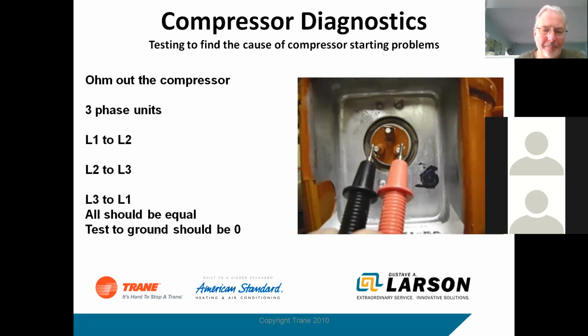The difference is, if you look at a true three-phase compressor, it's going to say L1, L2, and L3. And on an inverter-driven piece of equipment, you're going to see U, W, and V. That's an international symbol for inverter-driven equipment. So if you see U, W, and V, that's a three-phase inverter drive compressor or inverter-driven motor. And they're a little bit different. Usually the higher the voltage, the lower the ohm value. So on a 440 volt three-phase compressor, you're going to see ohm values in the 0.6, 0.7 range.